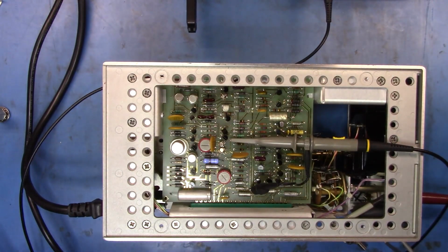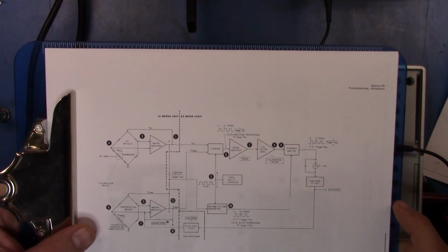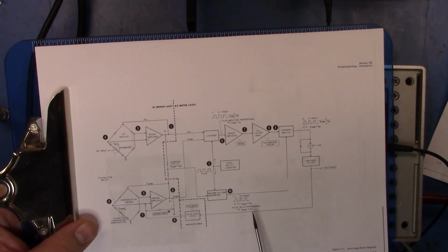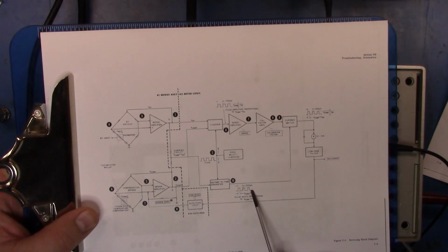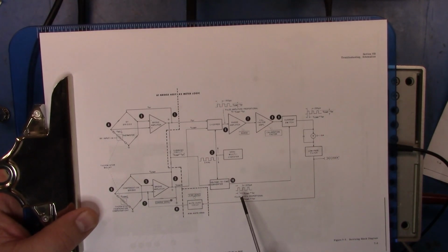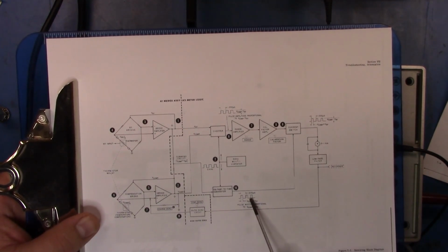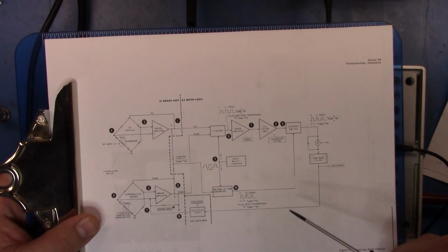So what is that telling us? If we come back here, what we're seeing is that our voltage-to-time converter, this guy here, should be giving us 5 kilohertz, which is roughly what we're getting, and it's going to have the pulse width proportional to the compensation plus the RF.